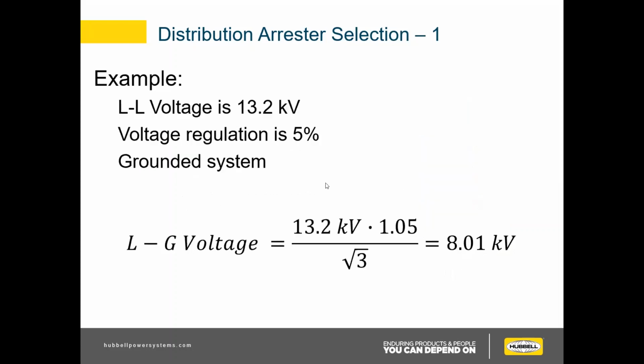So here's a quick calculation. We have a 13.2 kV system, line-to-line voltage. Our voltage regulation is 5%, and we can accommodate up to 10, 15%, whatever. We have a solidly grounded system for this example. So we have 13.2 times our 5% voltage regulation, divided by the square root of 3, which comes from your grounded system, and that gives us 8.01 kV. So that is the minimum MCOV that is required for your system.